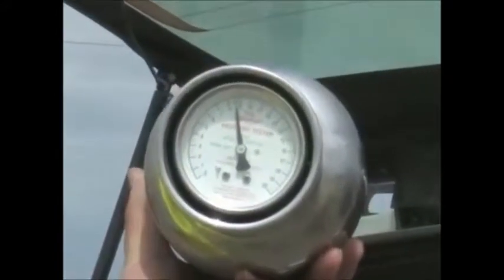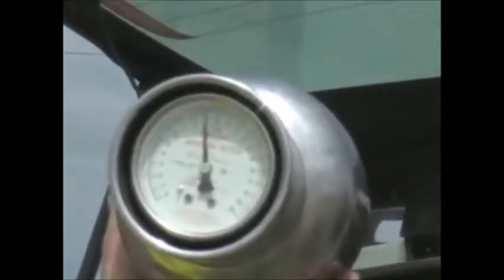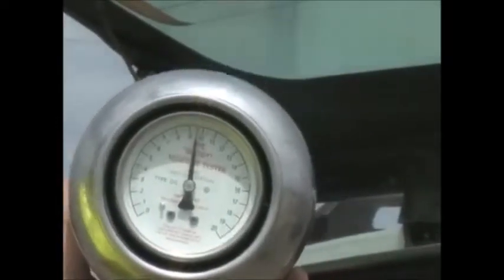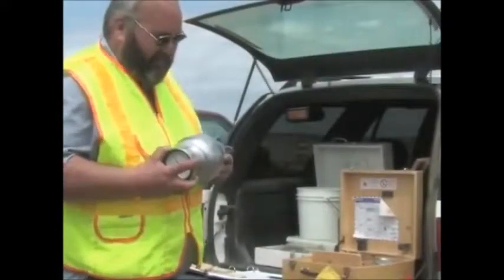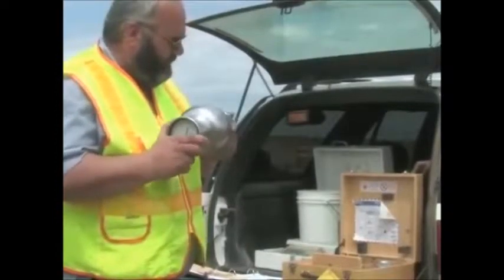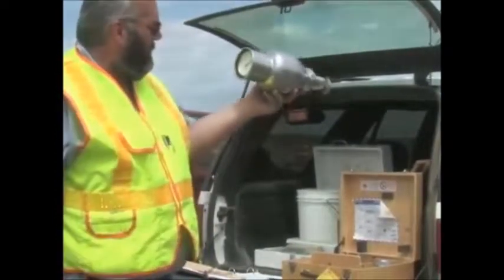The moisture-reagent mixture creates the pressure that is registered on the gauge indicating the moisture percent. Continue this cycle of shaking and resting for at least three minutes. Check the gauge reading after each cycle to see if there is an increase in the dial reading.